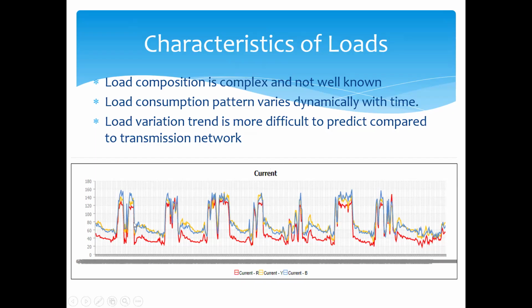So you can see this is a typical load curve of a distribution transformer. Not the load curve, but the current consumed by a distribution transformer over several consecutive days. You can see the pattern is not similar, it's varying. This may be a weekend, but the pattern varies. It's difficult to predict.